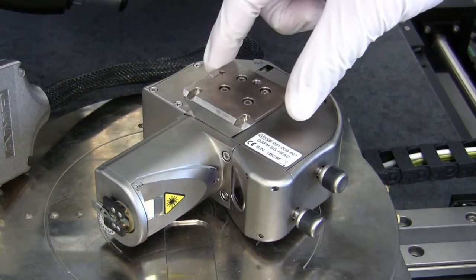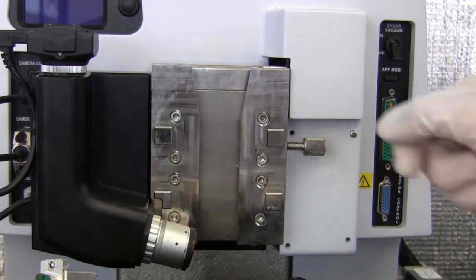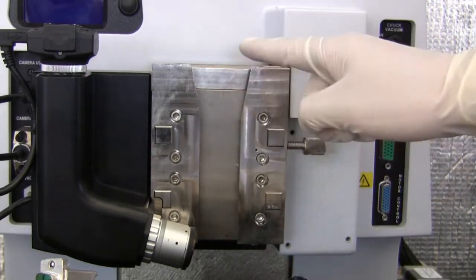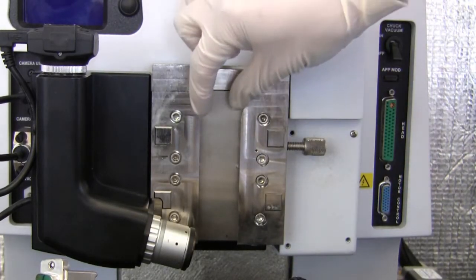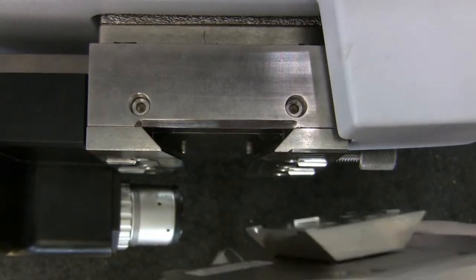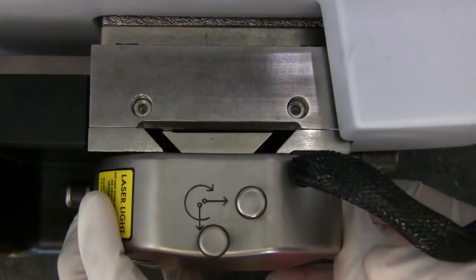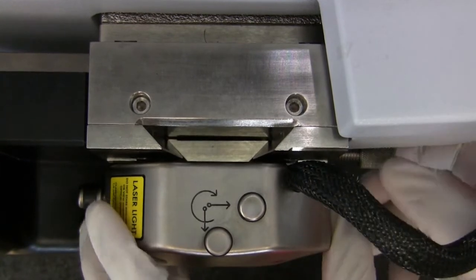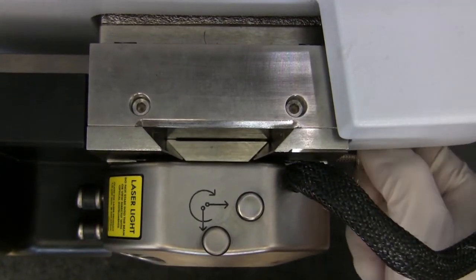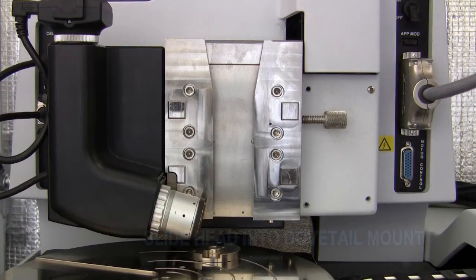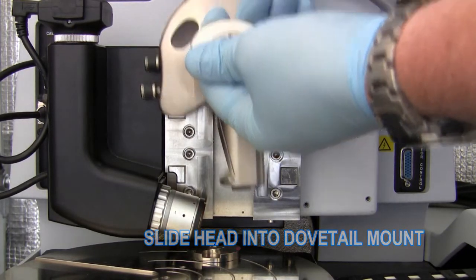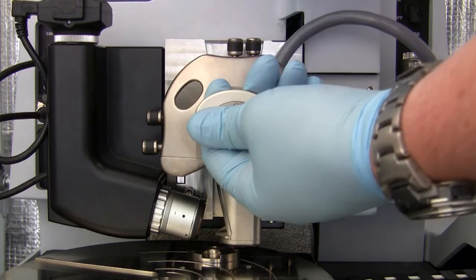The dovetail mount assembly consists of the fitting on the back of the scan head and the complementary vertical channel on the stage. Slide the head back into the dovetail mount on the stage and fasten it in place with the locking screw. Take care when placing the head in the dovetail mount. If the fixture is not aligned, you could drop the head, causing severe damage to the piezo.